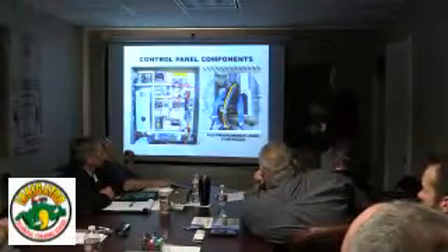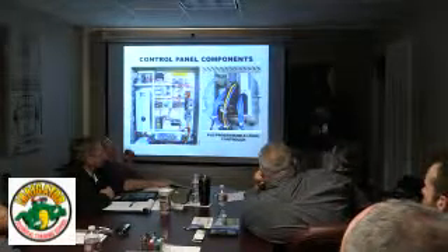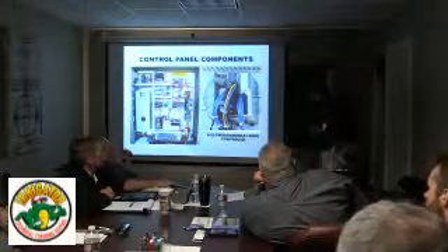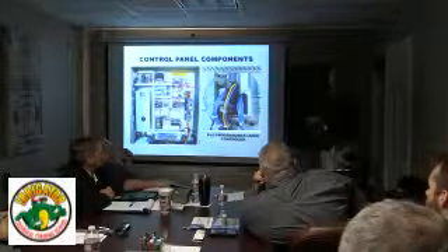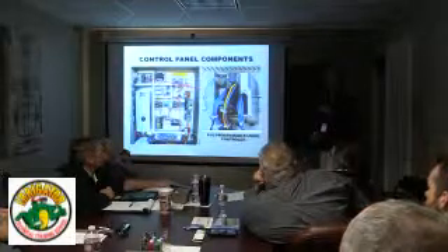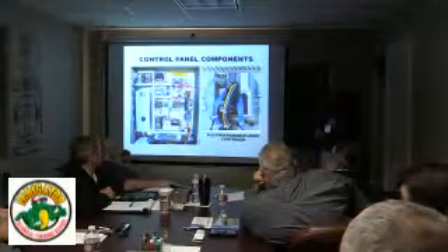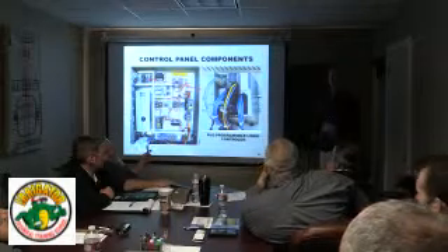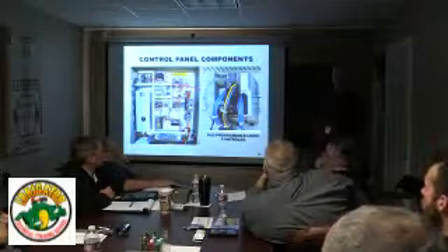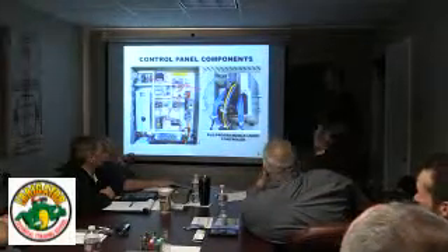That's an input. The reason why that might be so handy is, let's say you walk up to the panel and turn it into hand and nothing happens. Well, a lot of times those switches get dirty or dusty or something. If you just look on the schematic, find that switch, you'll see exactly what number it goes into on the PLC. Look over here, find that number. If you switch that switch from off to hand, you'll see that little LED go on, off, on, off. If you're not seeing any little LED go on, off, then the first thing I'd look at is the switch. Check the wiring there. It could be a major problem in the PLC or the programming or a fault or a high pressure shutdown, or for some reason it's not starting in auto, but in hand it should start.